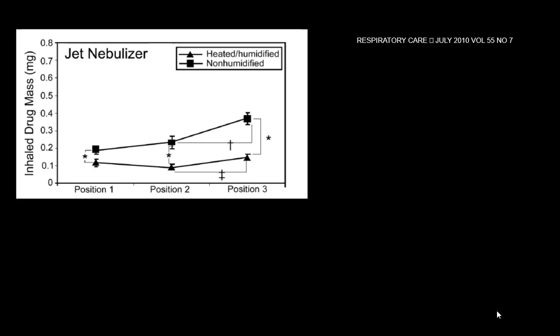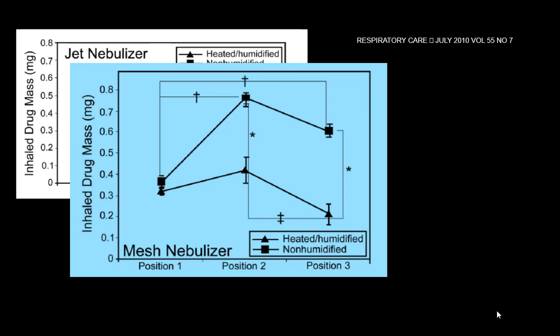So if you are using a jet nebulizer, it should always be as close to the ventilator as possible, because the amount of reservoir it requires to deliver a high dose of drug to the patient is high. So the more the reservoir, the more the drug will go into the patient in the next inspiratory flow. If you are using a mesh nebulizer, position 2 is better. Same for ultrasonic nebulizer, but if you use a PMDI, it really does not matter. 1 and 2 do not make any difference.